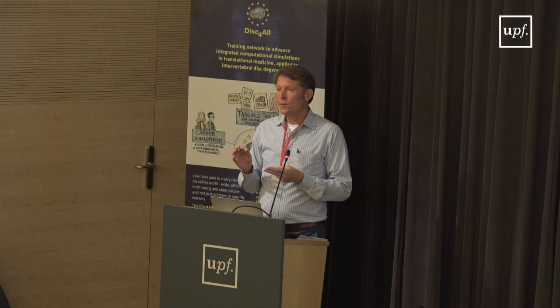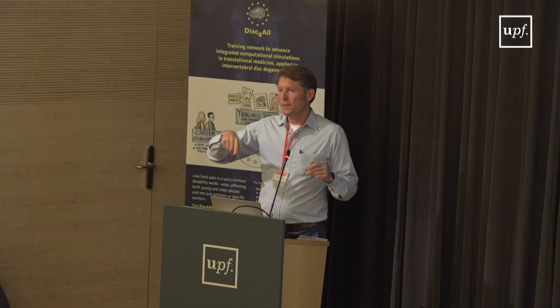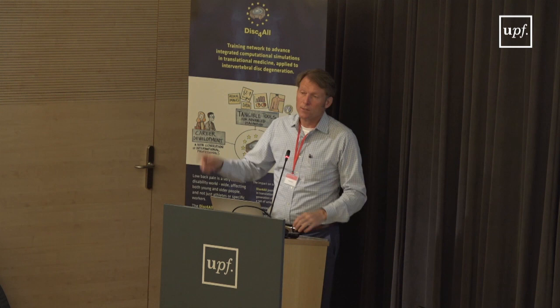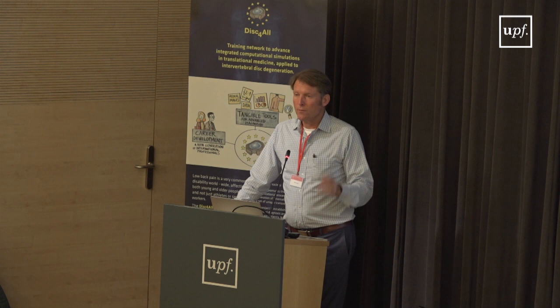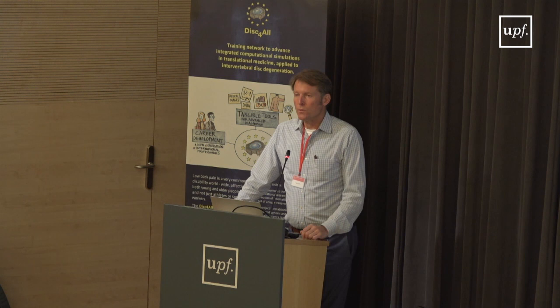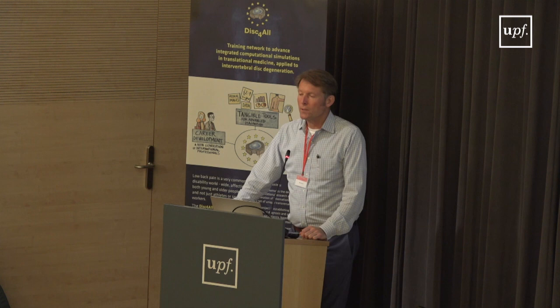The example I'll give you is the Womersley flow problem. If you're not familiar with that, it's a pulsatile flow in a pipe, idealized to the point where you just have a straight tube and a Newtonian viscosity, and you have a periodic solution for that flow. There's a group of us within the V&V 40 standard working on this Womersley flow problem. I did the code verification using Fluent, and another group was also using Fluent. They kept saying, every time I get the wrong answer, wrong answer, wrong answer. You need a UDF, a user-defined function, to apply that periodic velocity at the inlet.